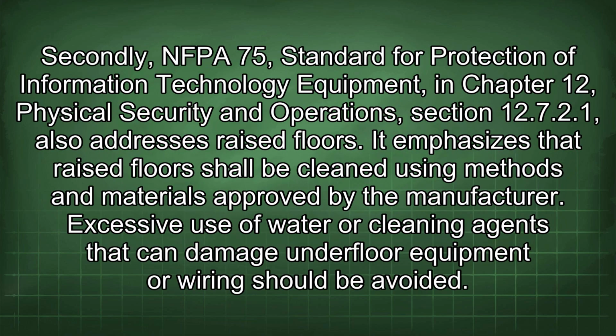Secondly, NFPA 75 standard for protection of information technology equipment in Chapter 12, Physical Security and Operations, Section 12.7.2.1 also addresses raised floors. It emphasizes that raised floors shall be cleaned using methods and materials approved by the manufacturer. Excessive use of water or cleaning agents that can damage underfloor equipment or wiring should be avoided.